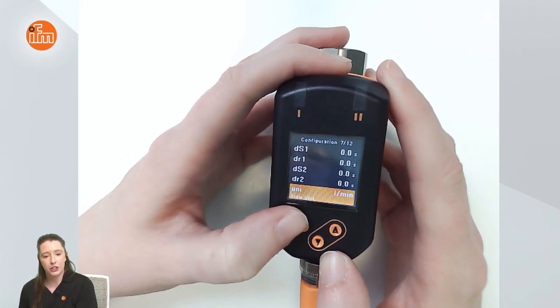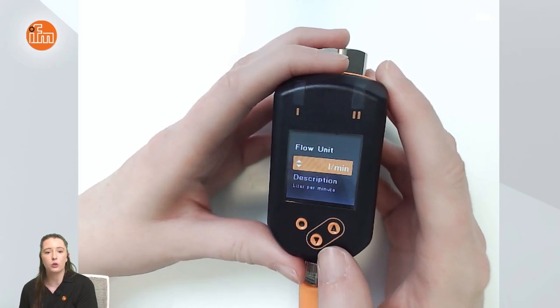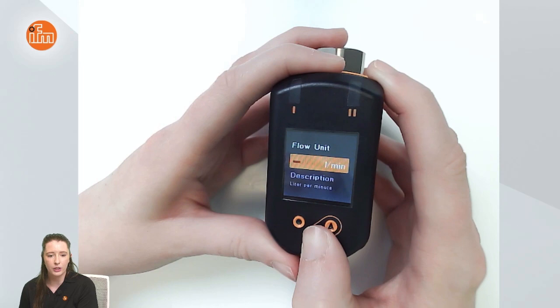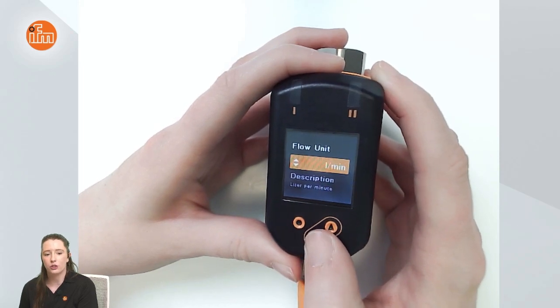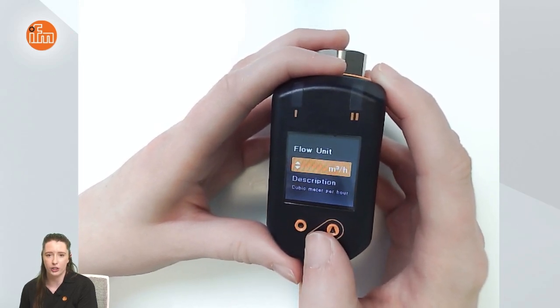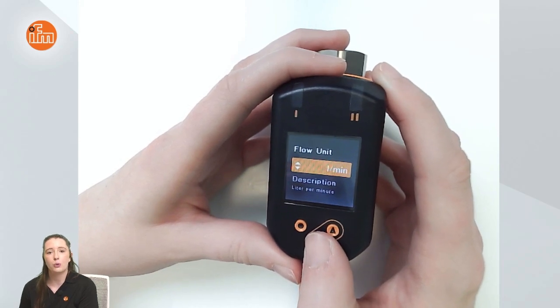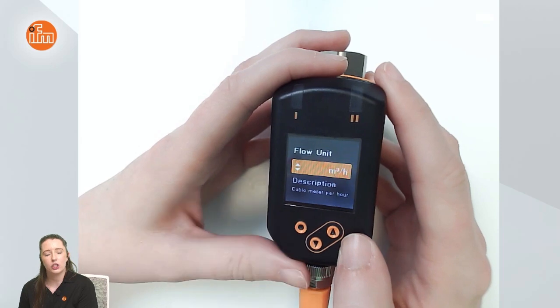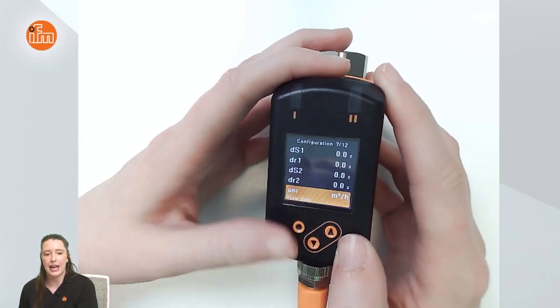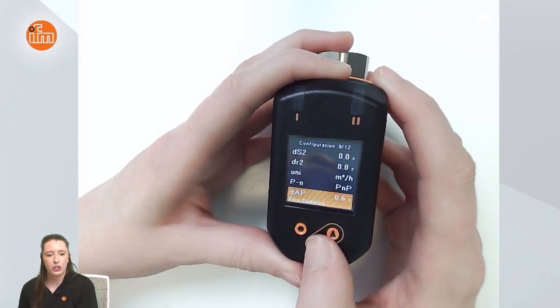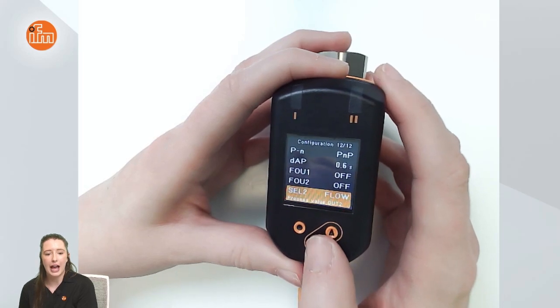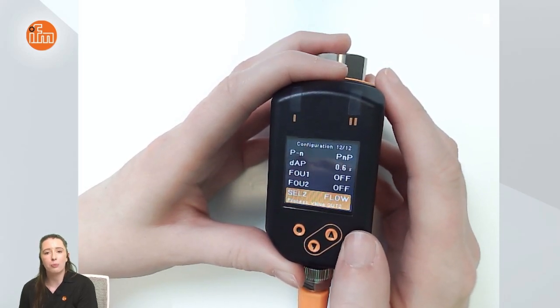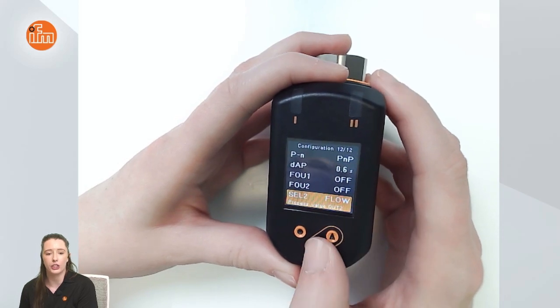If you press Enter at UNI it'll take you into this parameter, and if you hold down either the up or down arrow key you'll see the bar begin to load, and when it loads all the way you can toggle through your different options — for example liters per minute or cubic meters per hour. I will set it to cubic meters per hour by pressing Enter. Next I wanted to show you the SEL2 setting, which is where you can set Output 2 to either monitor flow or temperature.